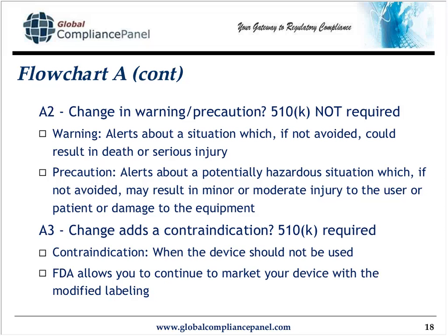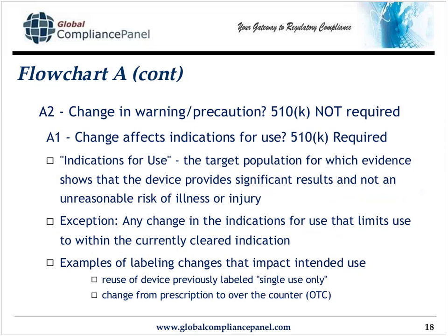A contraindication is when a device should not be used. So what you're doing is you're realizing, based on some data, that there are situations in which your device shouldn't be used. Previously, you thought it was okay, but now you don't think it's okay. The FDA definitely appreciates you taking care of this on their behalf, so it allows you to continue to market your device with the modified labeling till the 510K is approved. So you must submit, but you can continue to market at the same time.